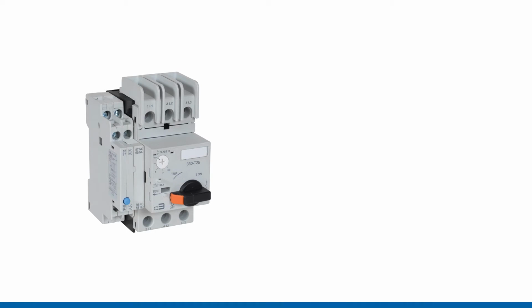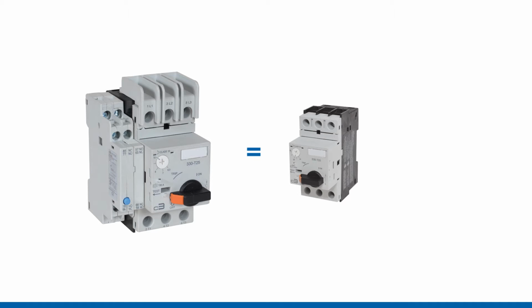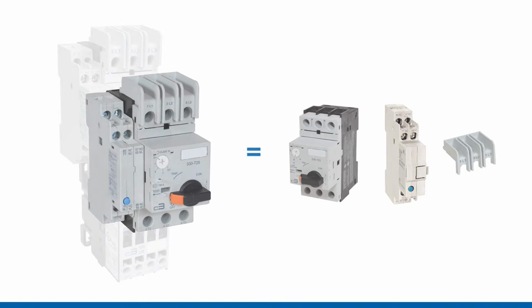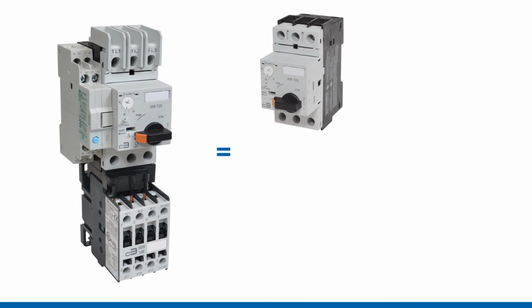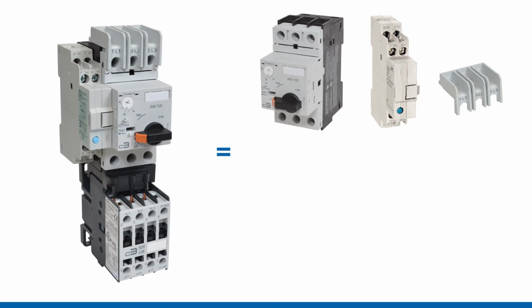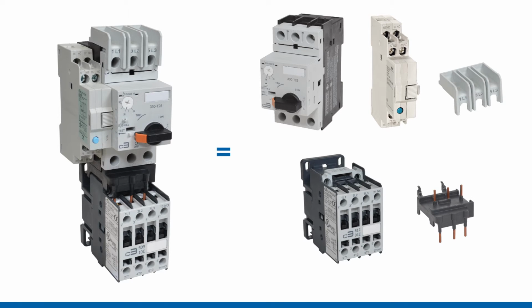Elements of a manual Type E device would include the motor protection circuit breaker, trip indicating auxiliary, and line side terminal barrier. Elements of an electromechanical Type E device would include the motor protection circuit breaker, trip indicating auxiliary, line side terminal barrier, contactor, and generally some type of link module between the motor protection circuit breaker and the contactor. However, the link module is not required, but as a complete assembly is generally offered.